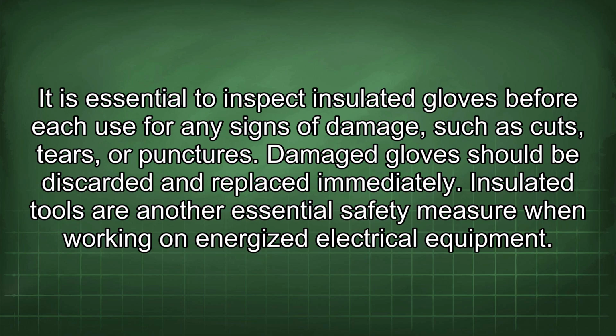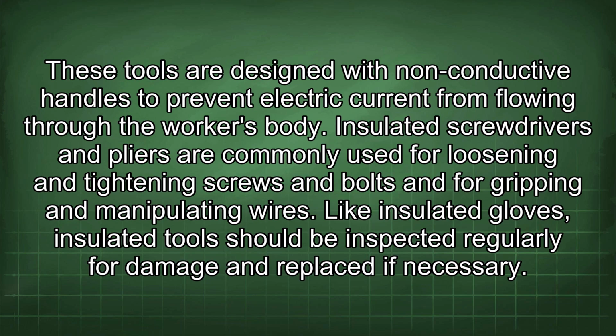Insulated tools are another essential safety measure when working on energized electrical equipment. These tools are designed with non-conductive handles to prevent electric current from flowing through the worker's body. Insulated screwdrivers and pliers are commonly used for loosening and tightening screws and bolts and for gripping and manipulating wires. Like insulated gloves, insulated tools should be inspected regularly for damage and replaced if necessary.